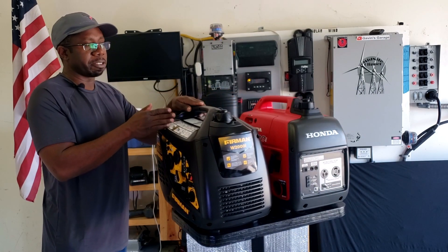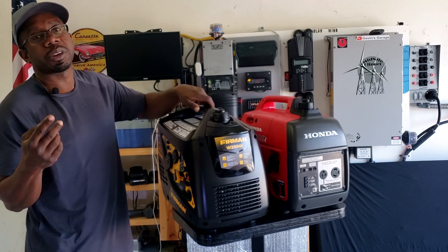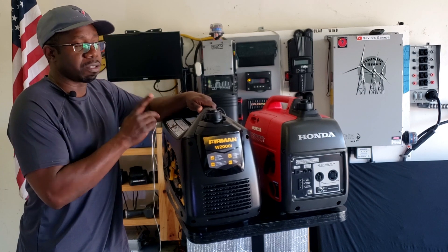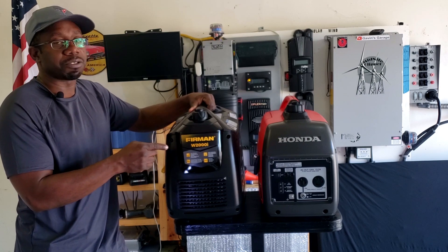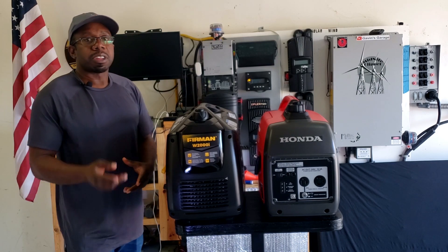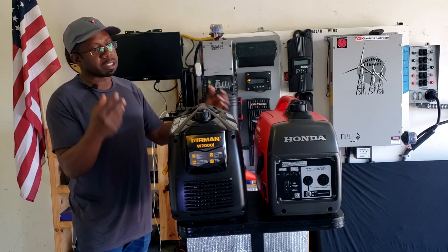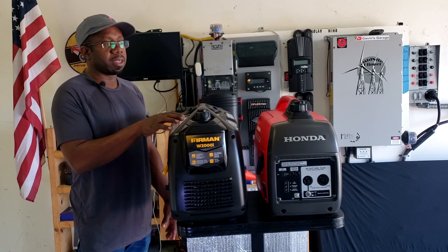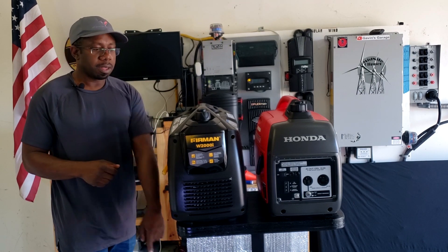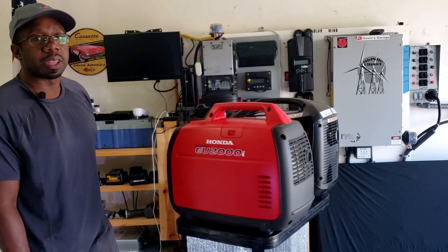So now we're going to take these two generators outside, start all of them, do load tests, check the sound and weight. The reason I have these two generators is they're all 2000 watt peak and 1600 running watts — exactly the same. I'm not going to try to overload them, just make sure they can run their rated wattage. Anything over 1600 watts is good enough. We're going to do it in eco mode and see what they do.